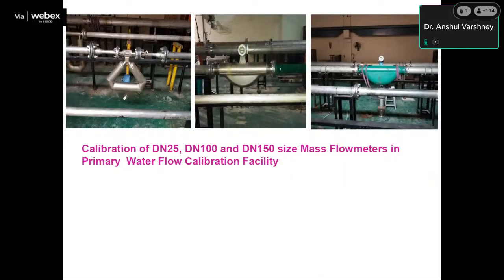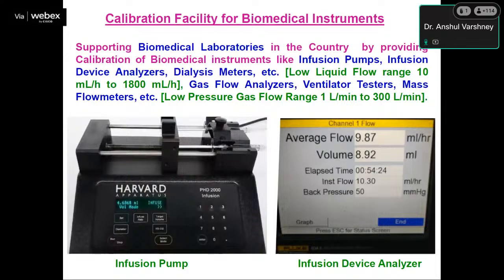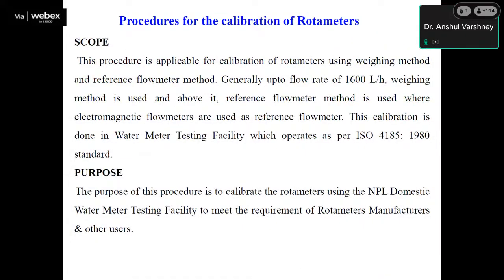This is the way we are mounting the flow meters in different lines, like 25 mm, 100 mm, and 150 mm. Now we have a calibration facility for biomedical instruments, called the low liquid flow calibration system, which is supporting biomedical laboratories in the country by providing calibration of biomedical instruments like infusion pumps, infusion device analyzers, dialysis meters, etc. This part I am skipping.